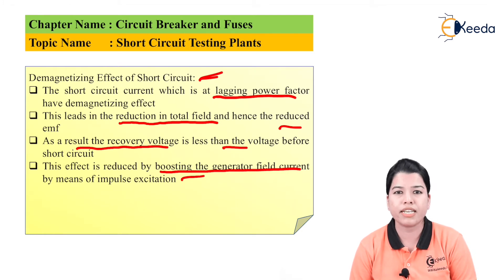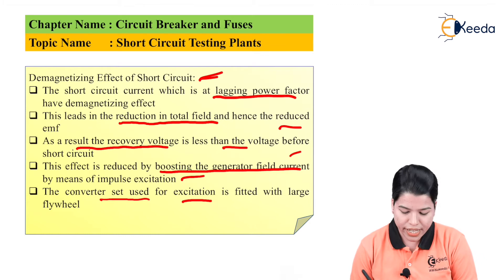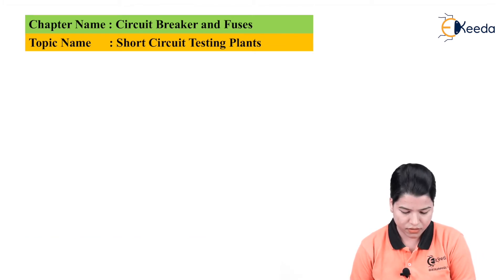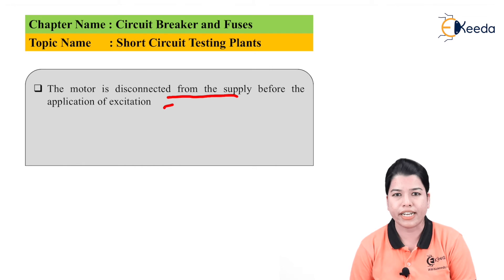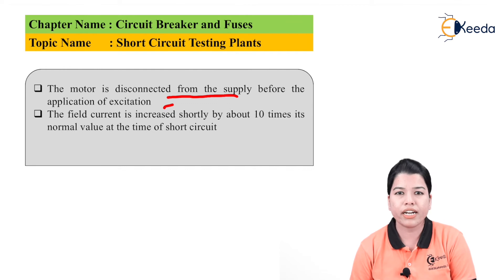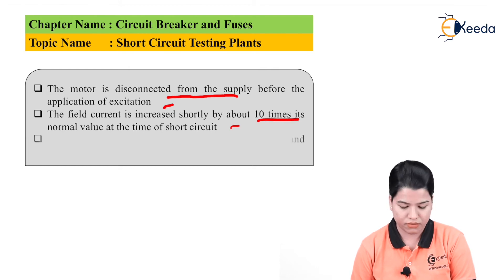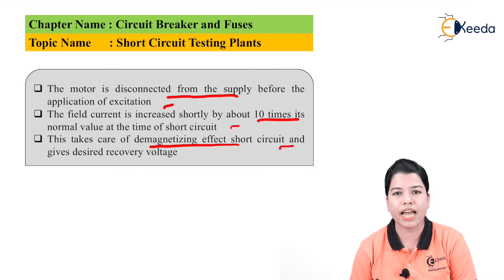The main aim of impulse excitation is to boost the generator field current so that the demagnetizing effect of the short circuit can be reduced. The converter set used for excitation is fitted with a large flywheel. The motor is disconnected from the supply before applying impulse excitation, and the field current is increased by about 10 times its normal value at the time of short circuit, taking care of the demagnetization effect and providing the desired recovery voltage.